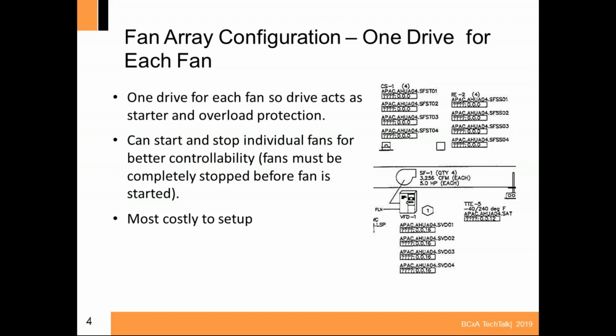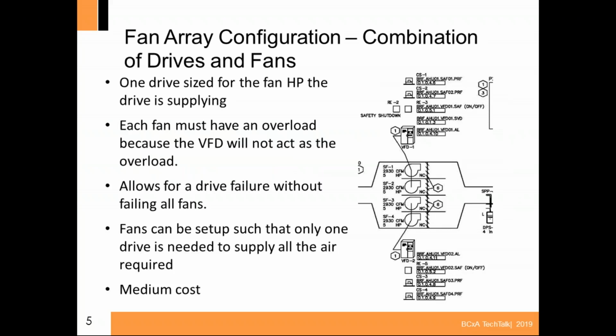And in that case, you have a smart program, which some vendors have, that can go in there and figure out which drive and which motor needs to drop out, because we'll talk a little bit about energy efficiency. You'll see what happens when we start getting motors part loaded and VFDs part loaded, and what really happens to the efficiency of the electrical setup. Now, the problem with this is it costs the most. Of all the fan arrays I've done, I've only seen this done one time, and this is the job you're looking at.